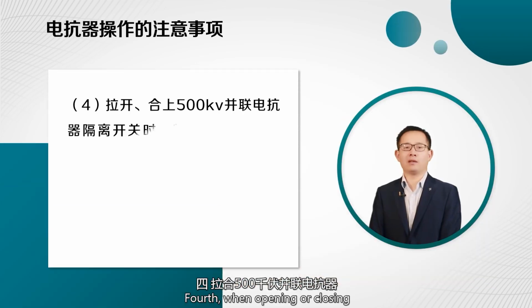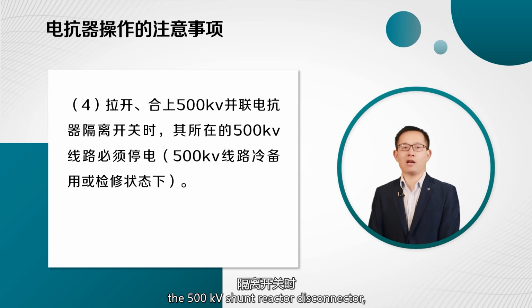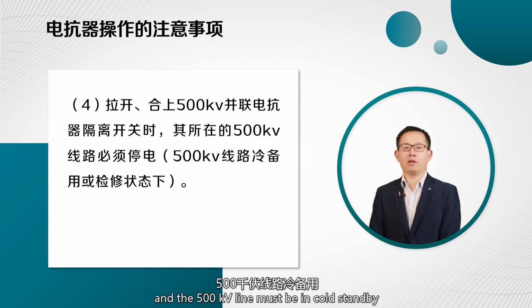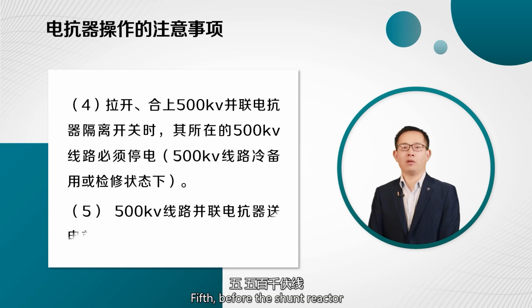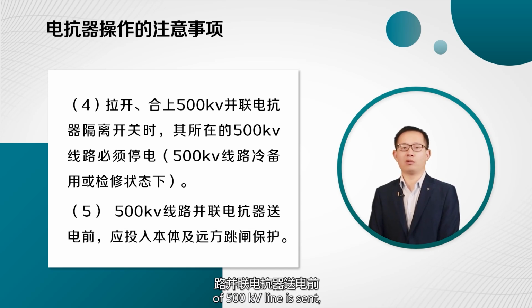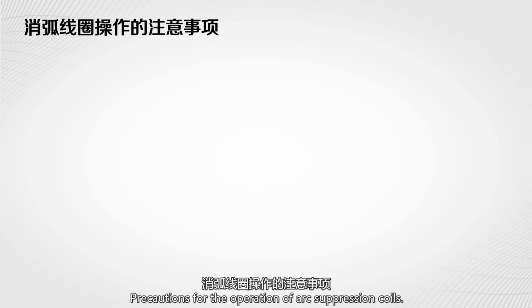Fourth, when opening or closing the 500 kilovolt shunt reactor disconnector, the 500 kilovolt line where it is connected must be powered off, and the line must be in cold standby or maintenance state. Fifth, before the shunt reactor of the 500 kilovolt line is sent, it should be put into the main body and remote trip protection. Precautions for the operation of arc suppression coils.